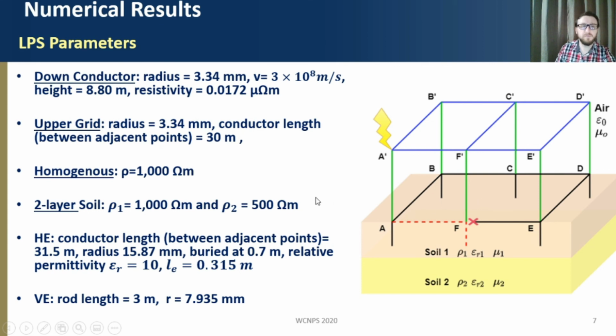Then our model will be studied using the upper grid represented by the J-Marti transmission line model, with the conductors represented as single transmission lines, and the ground grid system as horizontal and vertical electrodes. Here are the geometrical parameters and the soils, so two conditions. When we have homogeneous soil it would be 1000 ohm meters, and when we have stratified soil, 1500 ohm meters. And other details you can check in the article.